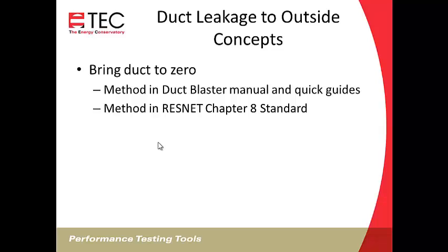And the goal of the test is to get zero pressure between the house and the duct. The closer we can get to that, the more accurate we're going to be able to read a reading of zero. And if you're using a type of gauge that has trouble reading zero, even without tubing connected to it, you're probably going to be better off going to 25. You'll probably get a more accurate reading that way than trying to go to zero.